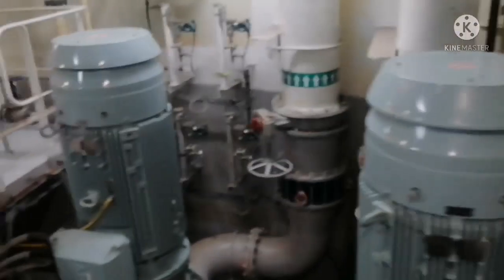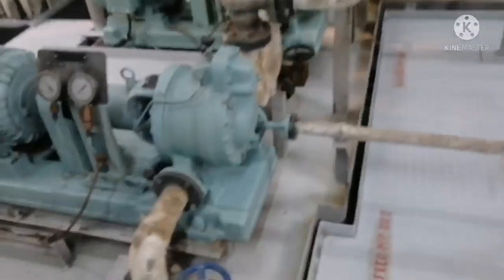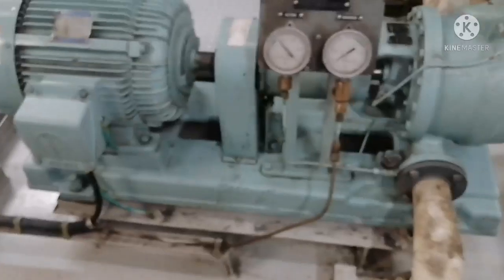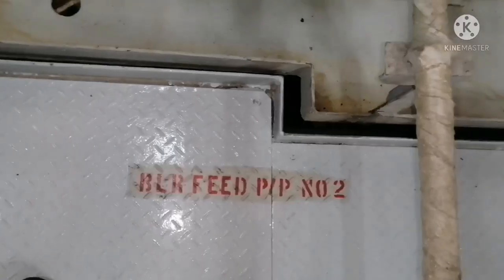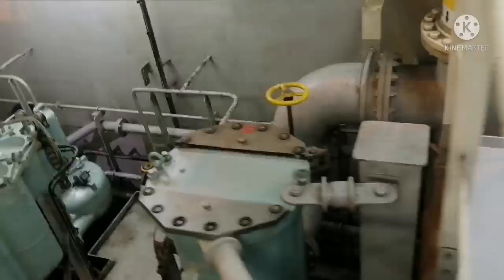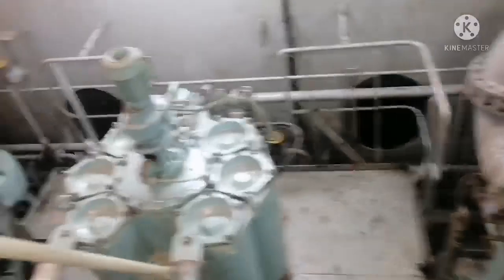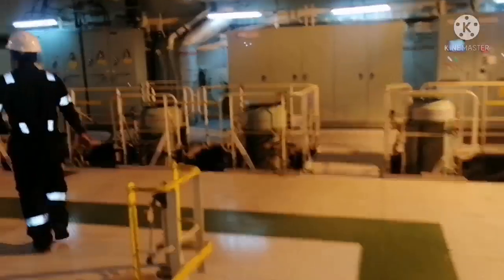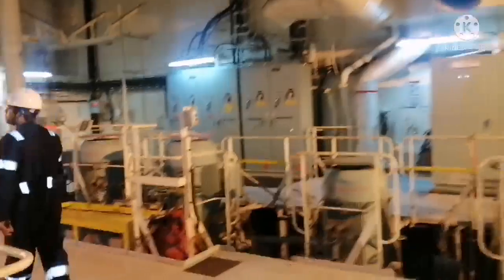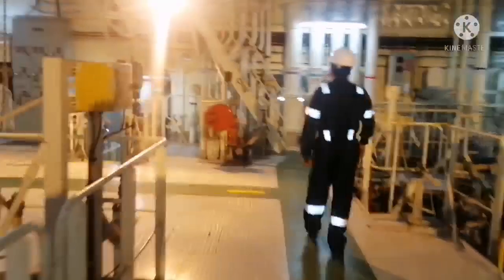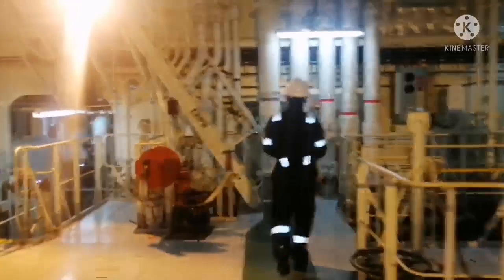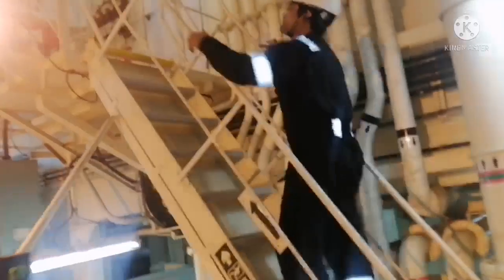Just check for proper pressure and everything, any leakage, nothing. So this is your boiler feed water pump. Just check for leakages, abnormal noise, any kind of vibrations and everything. This is your lube oil filter for your main engine. Just check for any leakages. Main thing during your UMS round, all you need to see is for any leakage, any unsecured objects, all these things you have to see.